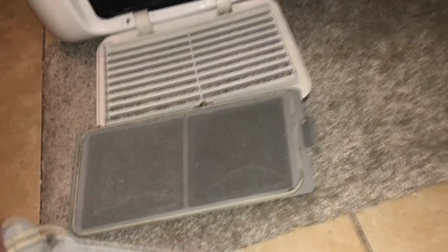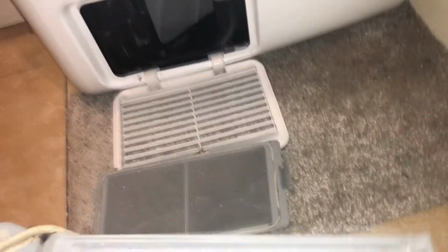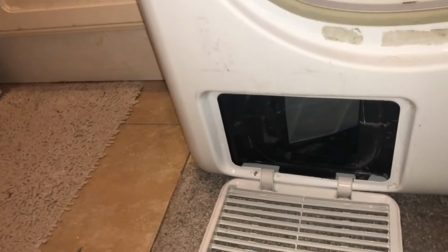That's the filter I told you has access from outside, but after 5 years I wanted to make sure the heat exchangers are clean and not contaminated. You get better access by opening the filters from inside rather than using a vacuum cleaner, which could cause damage. This is the primary filter, which stops the secondary filter from getting contaminated.